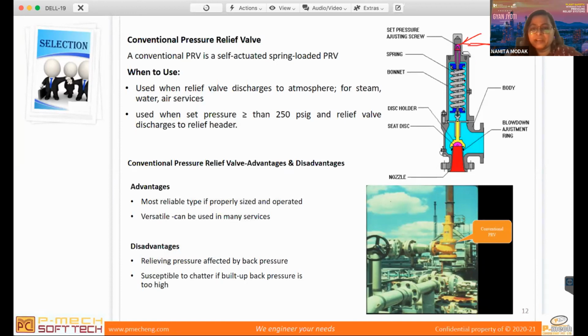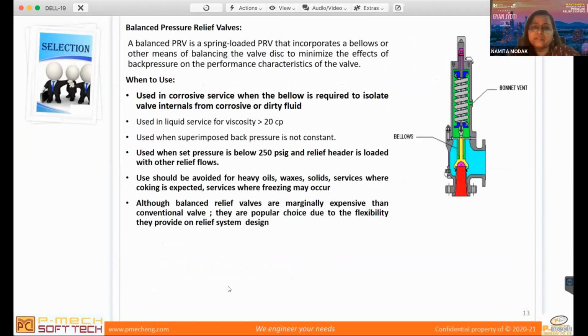The example which I say: let's say my set pressure is 10 bar gauge, and my back pressure, let's say, is 0.1 bar gauge. So my PSV will never open at 10. It will always open at 10.1. That is because of the back pressure which is acting on the spring. So this spring can be manually adjusted to that pressure so that it can save your system. So that is one of the disadvantages of the conventional type, and it is susceptible to chatter if the built-up back pressure is too high. We have already seen what chatter is. Then the bellows type, as I said, when the back pressure to set pressure ratio is 30 to 50%, we go with the bellows type of PSVs.